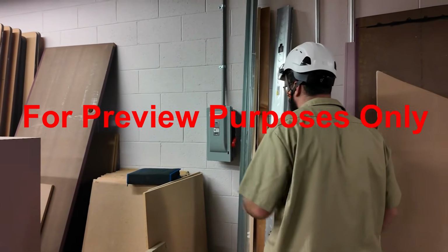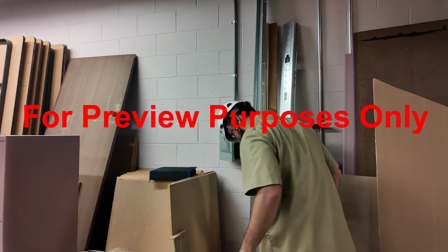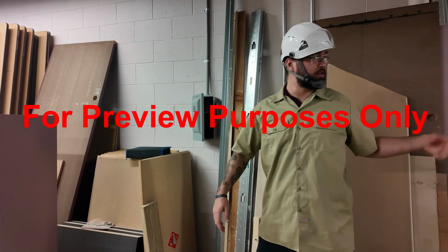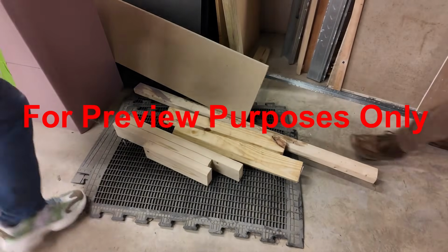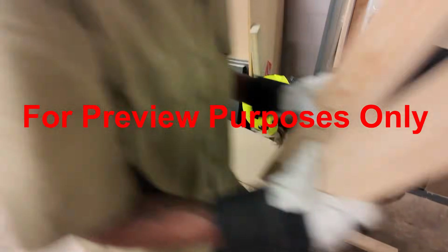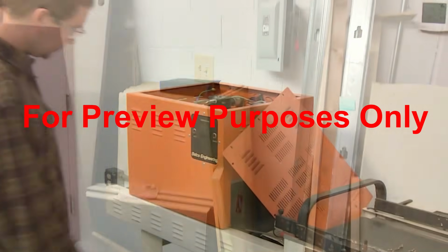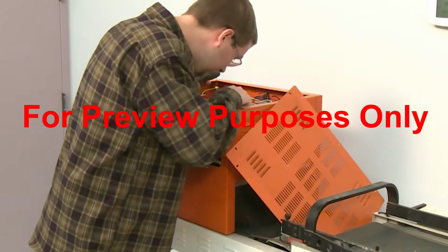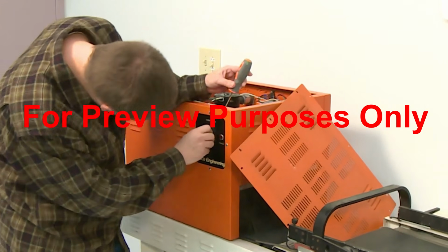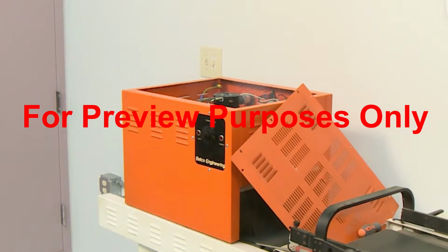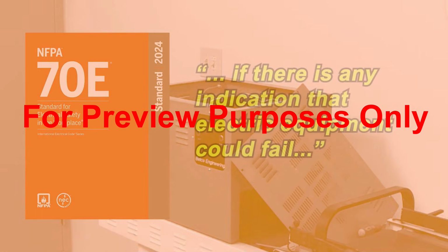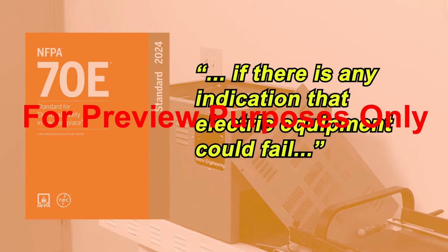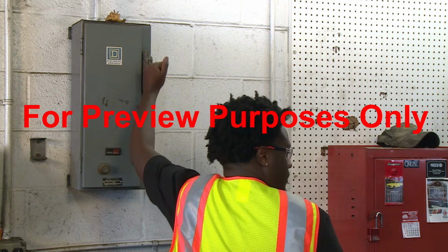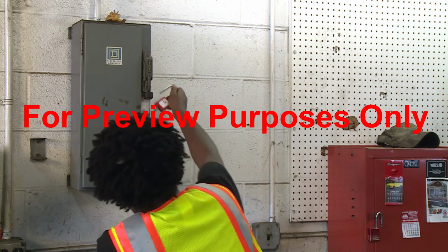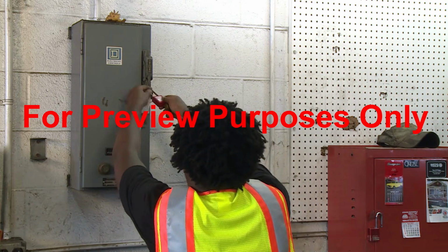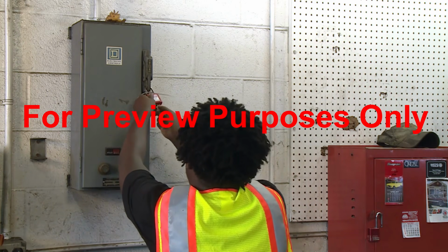If your job site is overcrowded or messy, it could prevent you from having clear access to the equipment or to escape passages. So before you start any project, always make sure the surrounding area is neat and clean. But in some cases, despite all of these precautions, the equipment that you're working on could fail on its own. So NFPA 70E advises that if there is any indication that electric equipment could fail, it should be de-energized immediately. If this does happen, you should not re-energize the equipment until the cause of the failure has been identified and repaired.